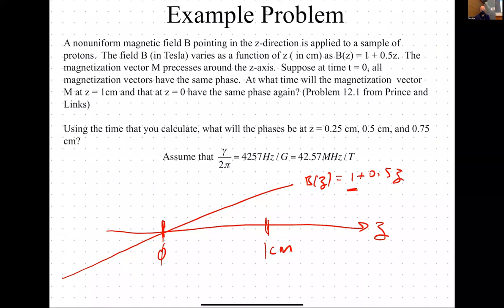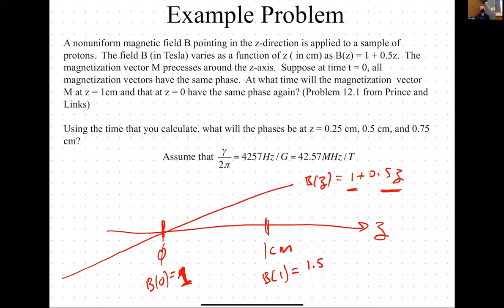So B(Z) = 1 + 0.5Z — this is like your B-naught field (the constant term) and this is the gradient term. B at Z=0 is equal to 1, and B at Z=1 is equal to 1.5. All we really care about is the difference in B field, because that gives us the net difference in frequency. So delta B is 0.5 Tesla. In the rotating frame of reference, the spin at isocenter is static — it stays at zero phase. The spin at Z=1 cm is in a higher field, so it spins faster; it has a relative precession.